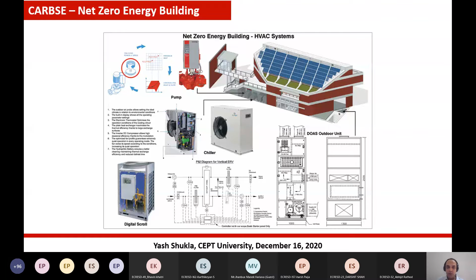How do we assess the performance of a typical air conditioning system? There is a metric called coefficient of performance. What that means is the cooling delivered by the system versus the watts of electrical energy consumption that it takes as input. So a certain wattage it takes as an input, and it produces cooling because of the refrigeration system, depending upon the type of refrigeration system. So COP is one metric, and in a different unit, when you convert it, you can also put it in what is called the energy efficiency ratio or EER. So these are the common metrics used to assess the performance of air conditioning systems.